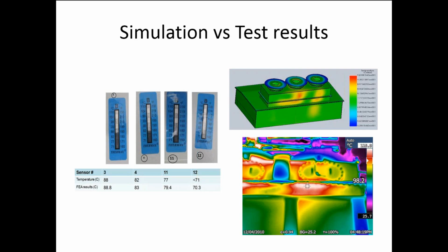So here is a thermal mapping. You can do the same. This is the temperature distribution that you see in the computer, and here are a few sensors, and how those locations compare with the simulation results.